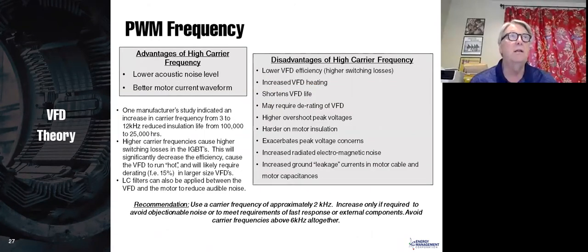So that sounds good. Let's just hike that carrier frequency all the way up, unless there are disadvantages. Well, there are some disadvantages of higher carrier frequency. The biggest one is lower VFD efficiency. Every time you switch those transistors on and off, they generate a little bit of heat. And the faster you switch them on and off, the more heat is created. If you go to the highest carrier frequency of the drive, you may find that you have 4 times as much heat being generated in the drive as at a lower carrier frequency. So that causes increased VFD heating. It can shorten the VFD life. It may require derating of a VFD.